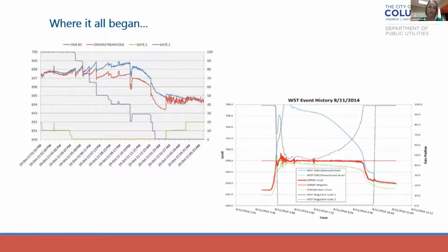This is probably nothing new to anybody on the call today, but it's one of those typical aha moments where we can show how this all worked out. What I'm showing here is an old graph on the left showing that incremental stepwise change in the gates and how it impacted levels in our system overall. To the right, once we implemented the automated controls, you can see a nice smoother graph that better controlled the gate positions, and ultimately the subsequent downstream flows. The red line running through the middle of the graph was our set point for the elevation in that particular facility, and you can see we are right on it with the automatic controls. So this was where it all started.